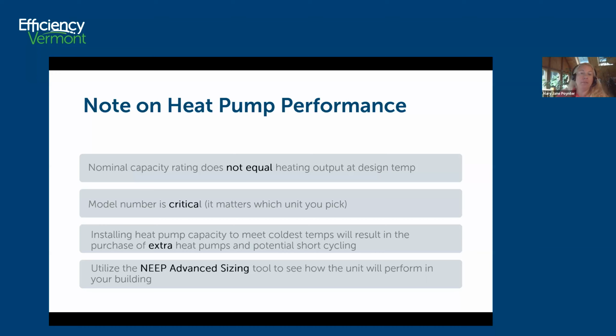And if you're installing heat pump capacity to meet the coldest temps, you'll end up having to buy either larger heat pumps or more heat pumps in order to have enough capacity when it gets really cold. If you need 2 tons and your heat pump is rated for 24,000 BTUs an hour at 47 degrees Fahrenheit, but it's only rated for 12,000 BTUs at 0, and you need the full 24,000 BTUs, you're going to end up having to either put in a larger heat pump or put in 2 heat pumps in order to solve that. And when you get heat pumps that are really oversized, you end up having short cycling when you're in the 30s and 40 degree outdoor air temperature.